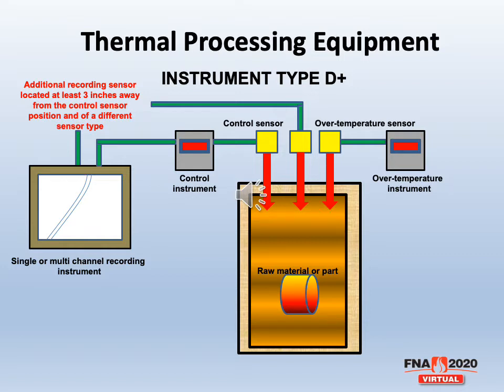For instance, if you had a type K controlling sensor and you want to go to the type D+ instrumentation type, that second recording sensor would have to be a different type. So you could use type J or type N or type S. And again, it has to be 3 inches away from the controlling sensor, and that sensor would have to be recorded.